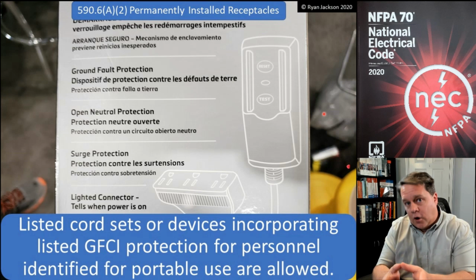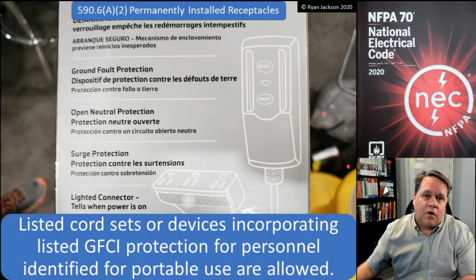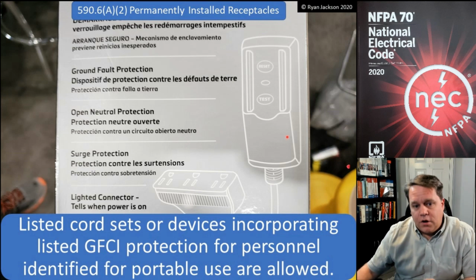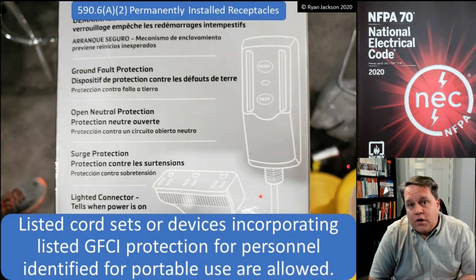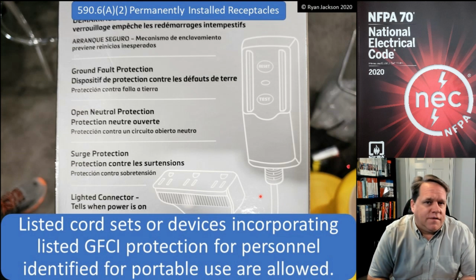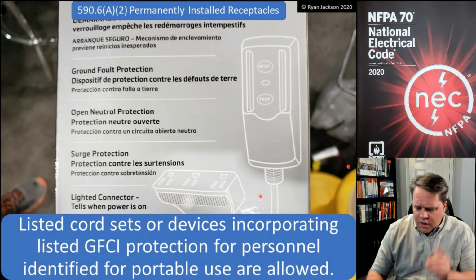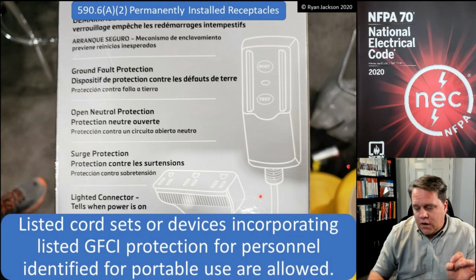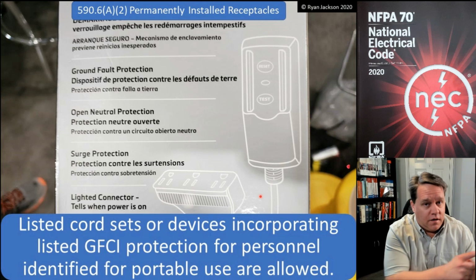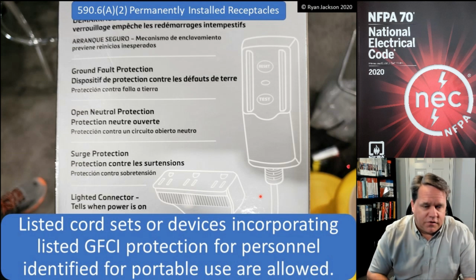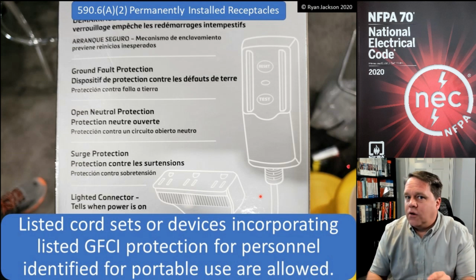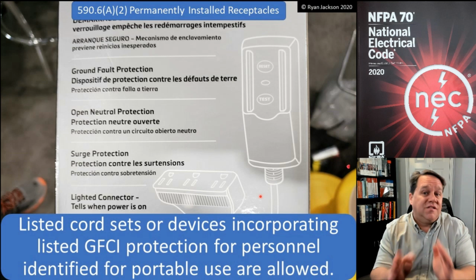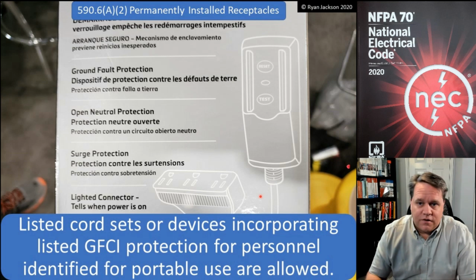And receptacles that are part of the building, your contractors are expected to provide their own protection. And we could use this language here in the code and probably justify that position. So this one seems to be allowing those devices instead of the protection of the receptacles. And again, I'm not positive that that's intended or not, but the two sections definitely read different.